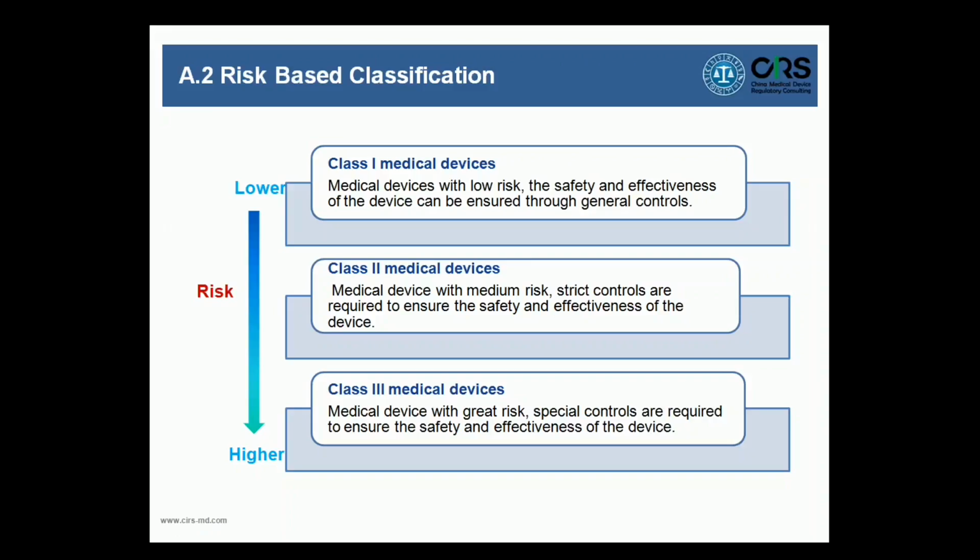Class 3 medical devices are with great risk. Special controls are required to ensure the safety and effectiveness of the device. The risk level here is evaluated by the intended purpose, structural features, intended use, and use methods of the medical device.